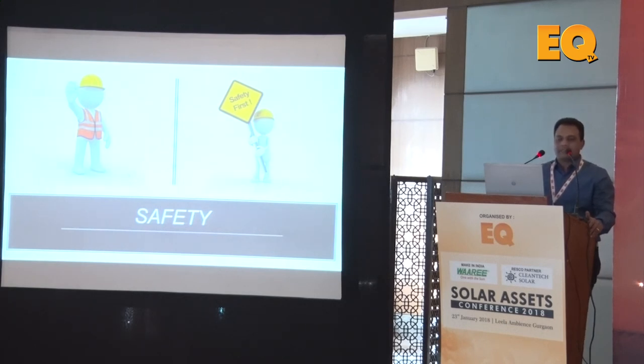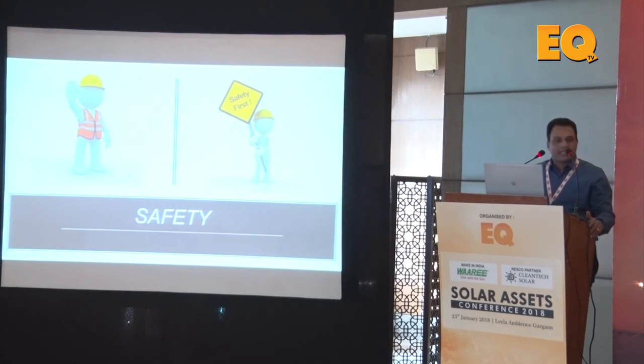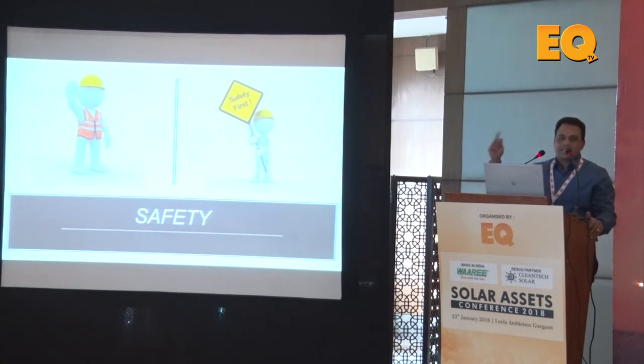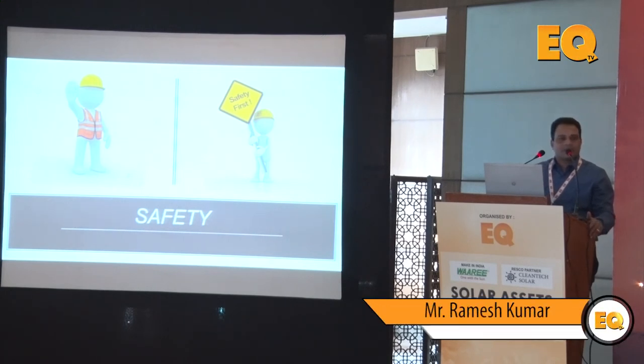Safety is a major area I personally feel strongly about in rooftop solar. In ground-mount solar, you have the luxury of four to five people on site, working in buddy pairs, which avoids many safety incidents. But in rooftop solar, the engineer travels and works alone, so you never know what happens. We introduced an on-call buddy pair system in coordination with the ROC — the site engineer talks to the ROC, which connects with another available person who calls the engineer every hour to check that he is safe.